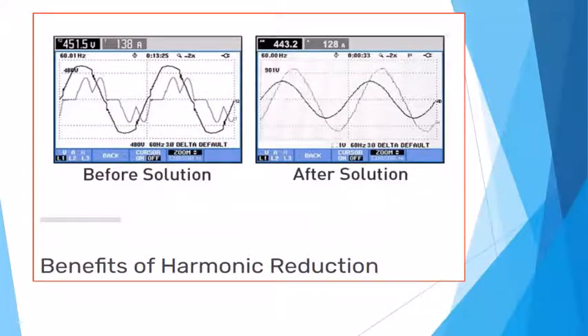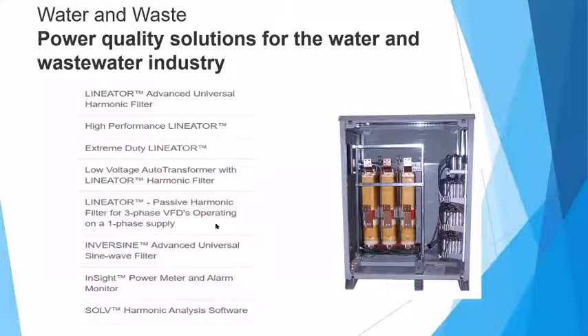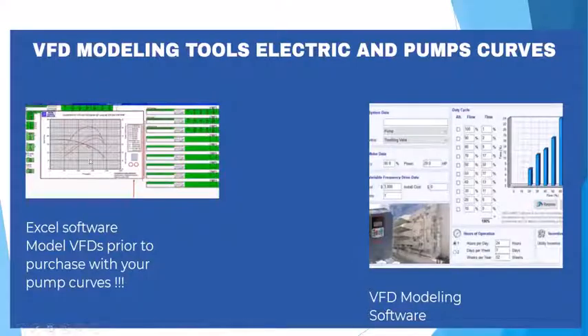So it's good to do a power study, look at where you're at, especially with a lot of VFD controls in your buildings, to get that as clean as possible, and do it as simple as possible, bring it back, and then look at the application. So if the pump is running off the curve, down here at, let's say, 70, instead of being at a 70 or 75% efficiency sweet spot, it's sliding down here into the 60s. All of a sudden, that 15% loss is lost there. So you've got 15% there. You've got 6% in the VFD.